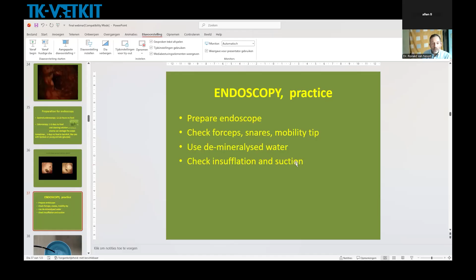For flushing during endoscopy, you normally have a little bottle on your endoscope. Please use only demineralized water. Check the insufflation and suction to see if they work, and you can do that most effectively by putting a little water in a small bowl, putting your endoscope tip in, and then closing the water and the air valve and seeing if there are enough bubbles. Because it's very frustrating if you are in the esophagus and you don't get the standard esophagus view. That can be because the esophagus is too firm, too hard to dilate, or it might as well be that you don't blow in the air at all. If you have to decide that when you are in the dog already, it takes a lot more time. So please check before if there's sufficient bubbling or not at all.